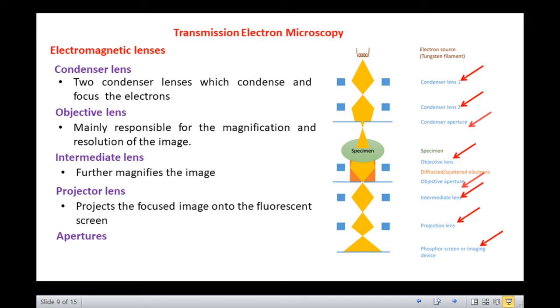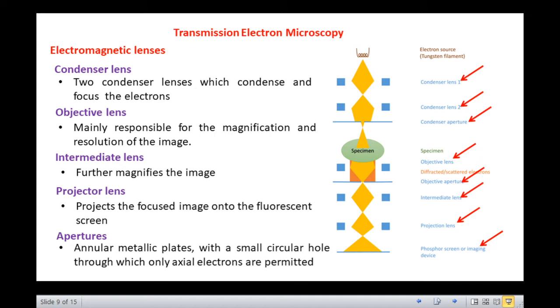These are annular metallic plates with a small circular hole through which only axial electrons are permitted. This permission of axial or central electrons decreases the beam intensity and also removes electrons that are scattered to high angles due to aberrations.